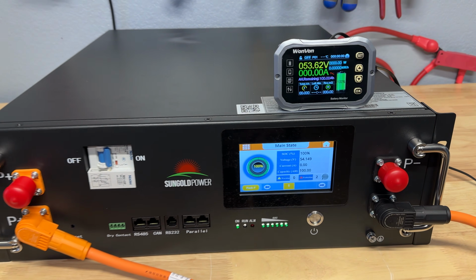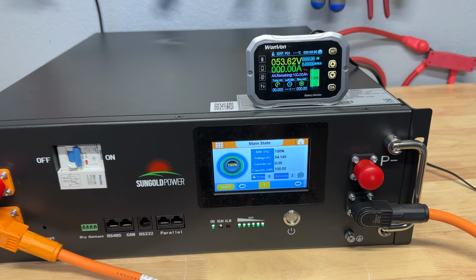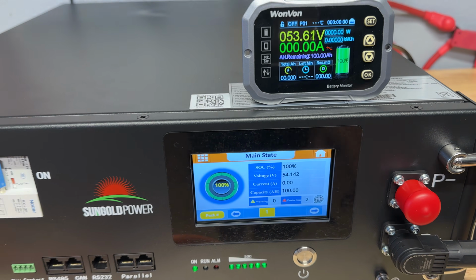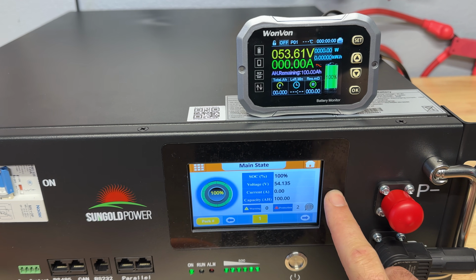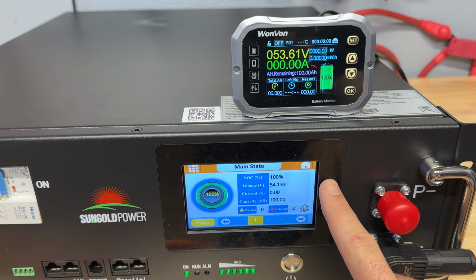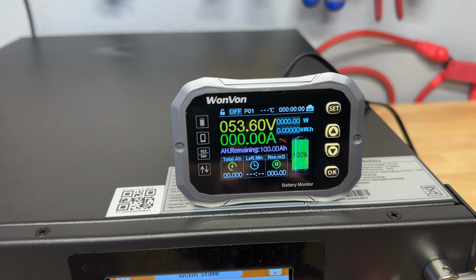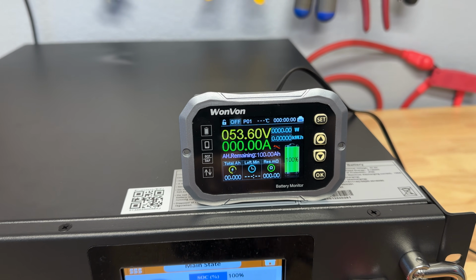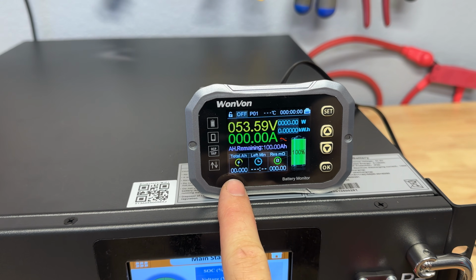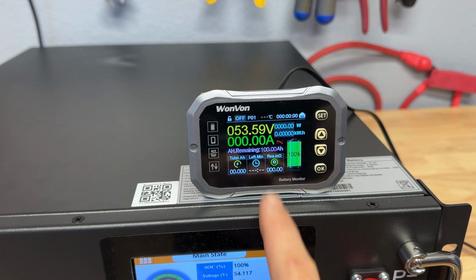Got our Sungold server rack battery fully charged. I think this thing has a coulomb meter to control the charging, because whenever it reached 100 it actually shut the charger off. It didn't shut it off when it got to like 58.4 or whatever. This is gonna be the capacity meter we're gonna use to see how much capacity we get. The total amp hours is gonna be displayed right here. This is all reset, set to 100 amp hours.